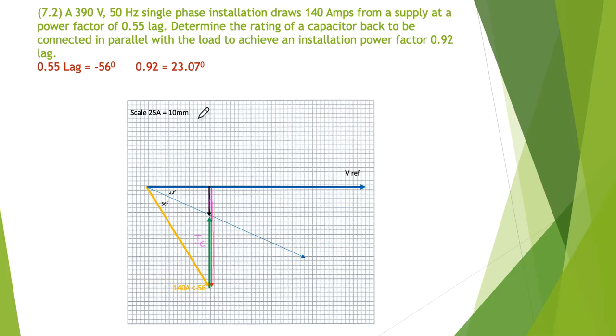If I've done my diagram very accurately I can actually scale that off, but I'm going to take you through the maths so you understand how we can do it mathematically with triangles. First, we can work out the blue side: cosine of 56 degrees multiplied by 140 gives me 78.2 amps. I know this side of the triangle is 140 amps long, the angle is 56 degrees, therefore I can use cosine to work out the blue side.